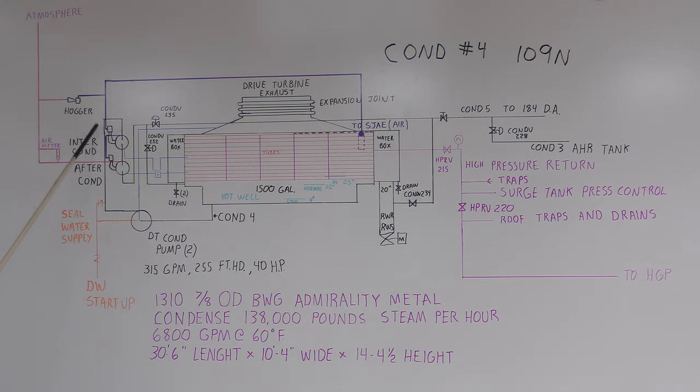It goes to the hogger that would use for startup. This uses steam pressure coming across and sent to atmosphere to pull a vacuum quick. We did a video on how the steam jet air ejectors worked a while back. It went to the first stage inter condenser - this pulled the vacuum. It had steam pressure coming in the top of the steam jet that created a vacuum.